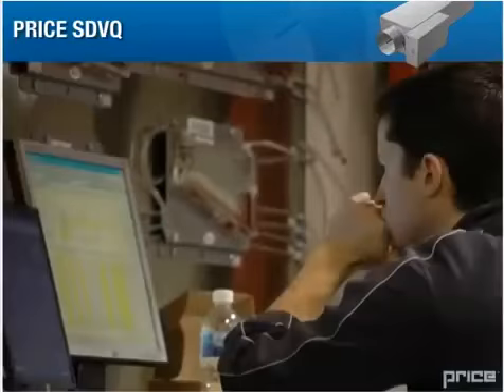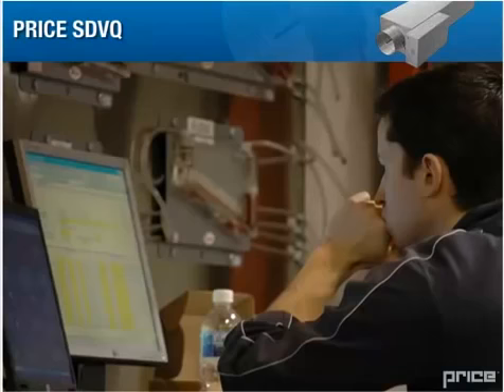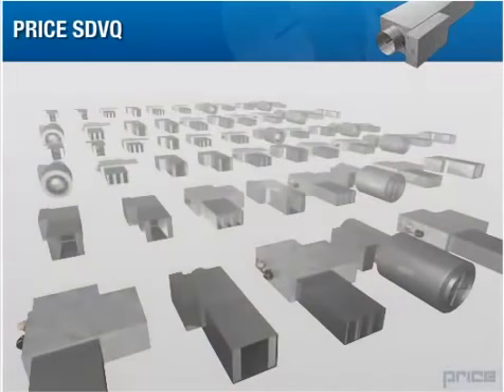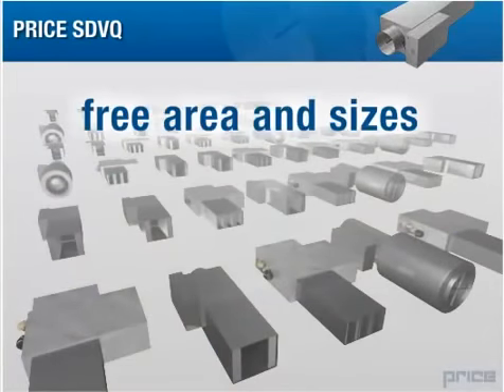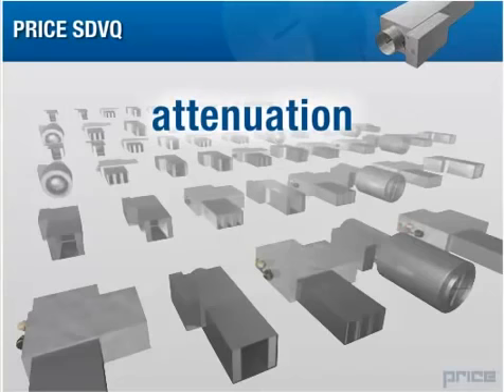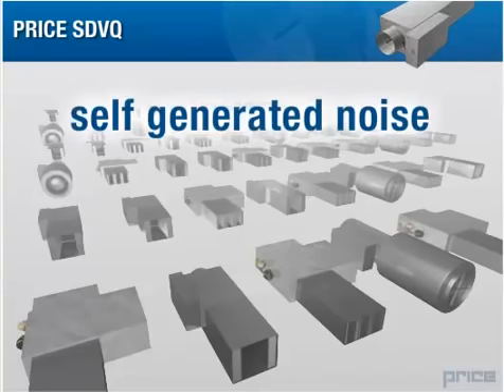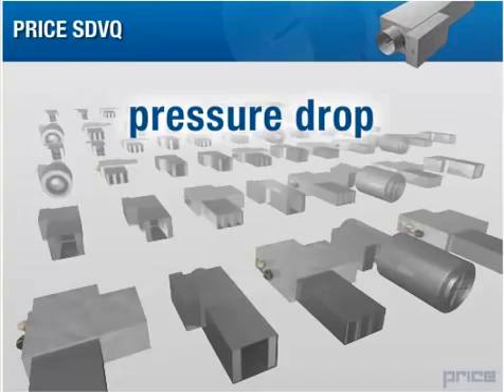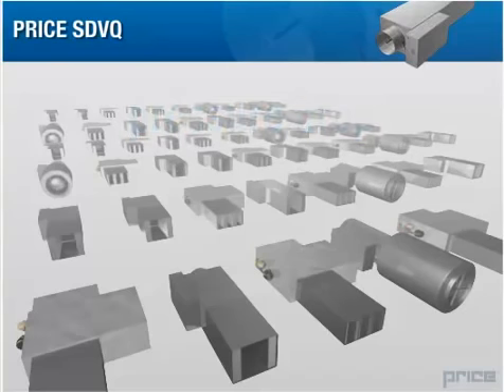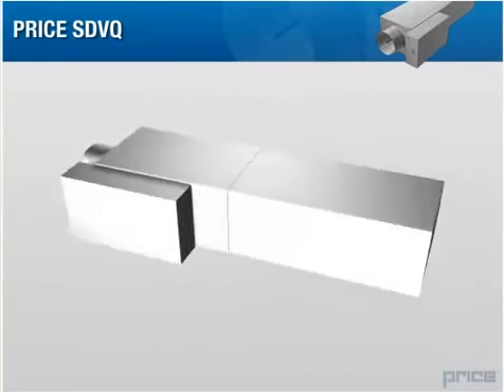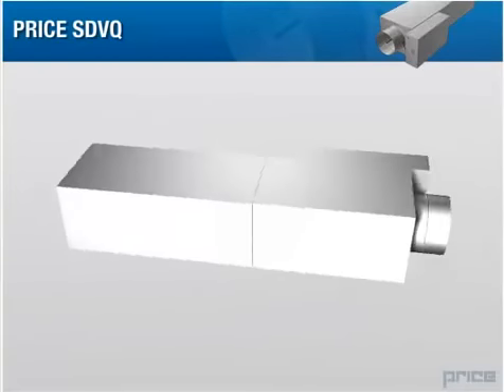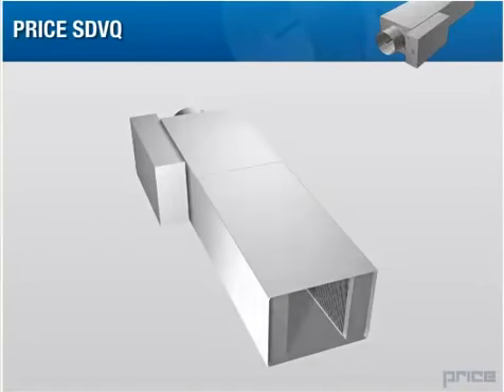In the past, selection of VAV terminals with silencers has been a complex and risky proposition. The designer had to select the silencer from a variety of available models, free areas and sizes, evaluating silencer attenuation, self-generated noise and pressure drop without really knowing the performance effect of a close-coupled silencer terminal combination. Price eliminates the guesswork by providing an optimized, fully tested, and certified assembly.